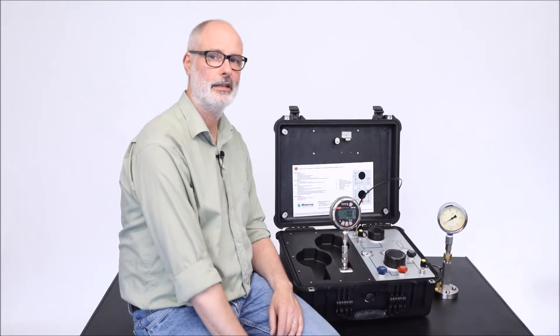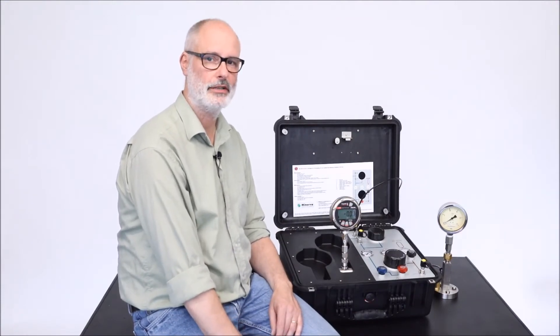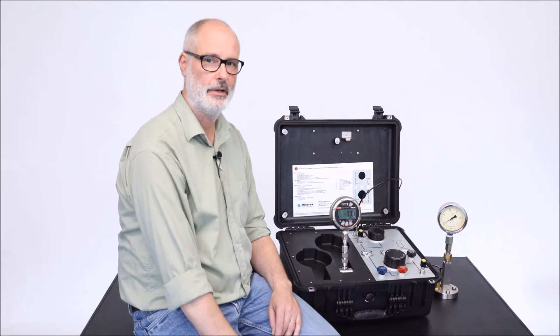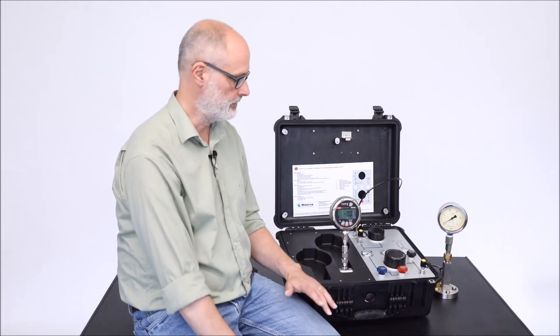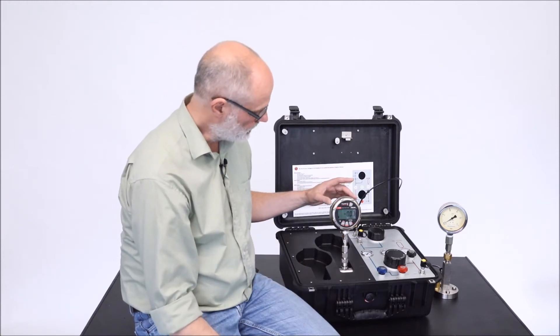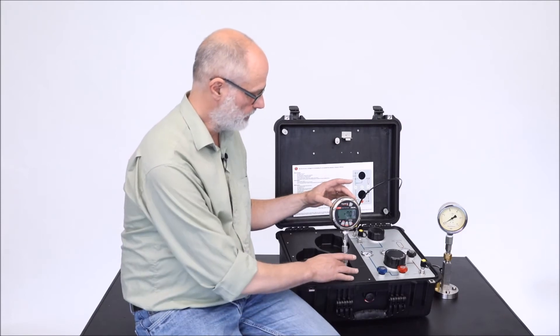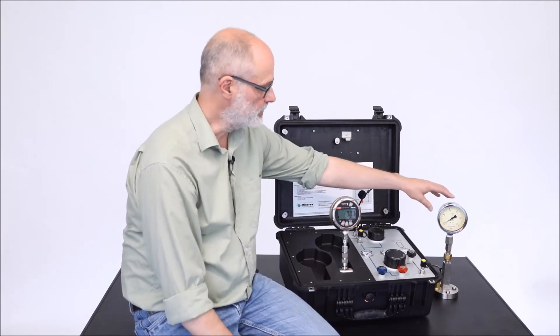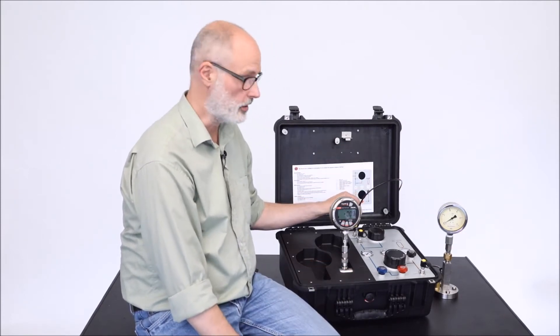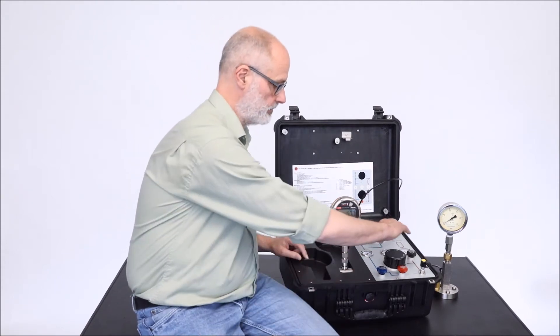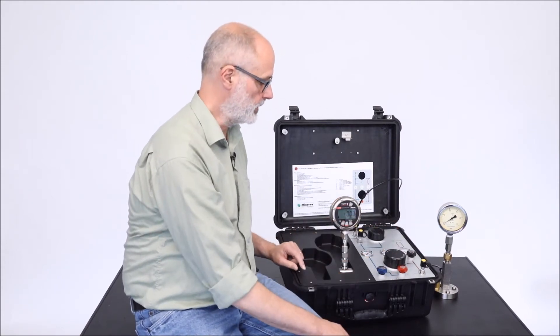Now I will demonstrate how to set a nominal stable pressure of 15 bar with the MNF300 high pressure case. I have connected a Crystal XP2i to my swivel and connected the device under test to one of the test ports. Now I am going to manipulate the valves to set the pressure.